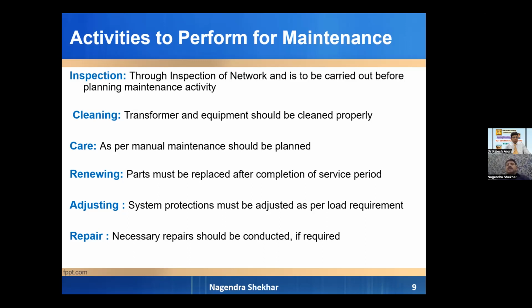Care. Care means basically whatever our manual of maintenance says. So when we have to change oil, when we have to tighten our nut bolts at what torque and so on. Renewing means basically we have to change certain parts which are required before they turn into any breakdown. Adjusting. System protections may be adjusted, realigned, reset as per the load requirements, or even the tightening of nut bolts if they require. Repairs. If we find that anything needs to be repaired, suppose jumpers are not connected well, or due to thermal stress or load stress the gap between two conductors is increased or the contact resistance has increased, we have to take action accordingly.